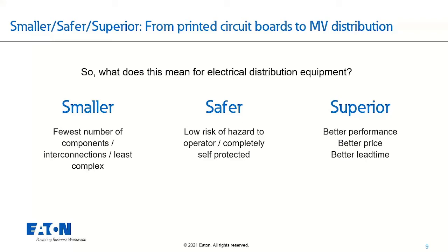But the other side to that is not just the operator, it's the safety of the piece of equipment as well. I've often encountered customers where we're installing some means of protection, targeting say an 8 calorie per centimeter squared incident energy, where the user can be in gloves and a face shield. In most cases, even at a level 1 PPE category, they'll probably still wear the gloves and face shield anyway, so why wouldn't you add that extra layer of safety? Those same customers will ask, what's the value proposition of going from a level 2, where I'm already wearing gloves and face shield, down to a level 1? Why would I need that if my users are already fairly safe? More safety for the operator is obviously better, but there's another piece to that puzzle: equipment safety.